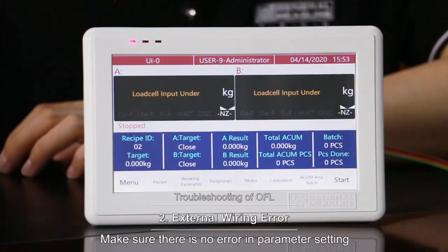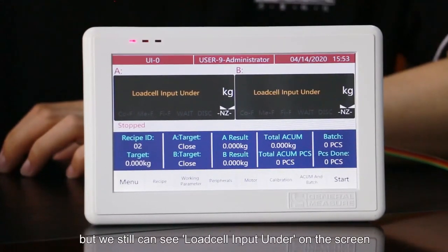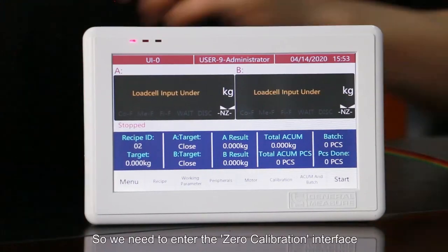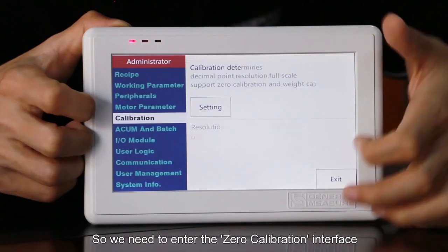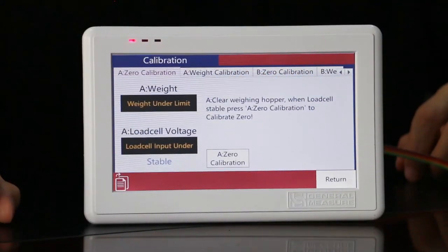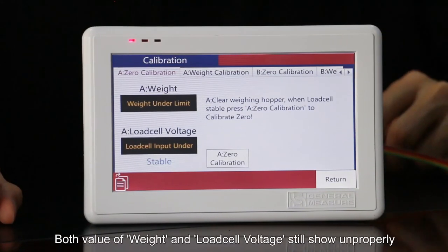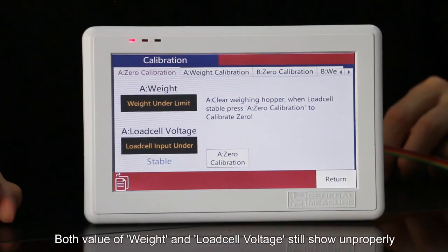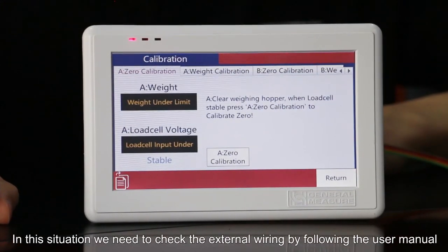Second, external wiring error check. Make sure there's no error in parameter setting, but we still see a Loadcell Input Under on the screen. So we need to enter the 0 calibration interface. Meanwhile, press the weighing platform. Both values of weight and load cell voltage still show improperly. In this situation, we need to check the external wiring by following the user manual.